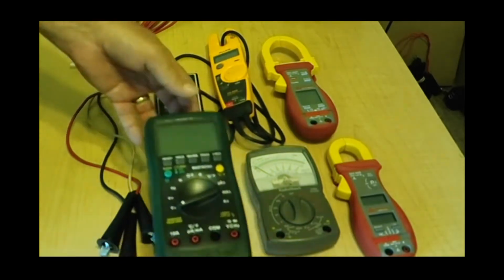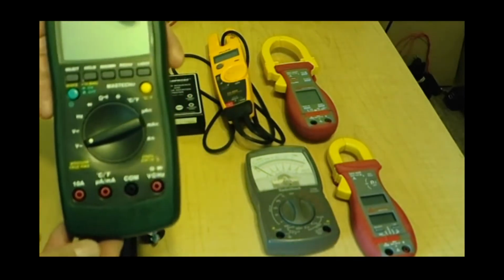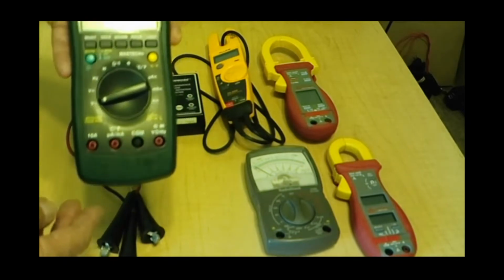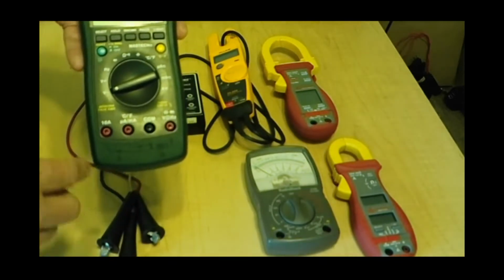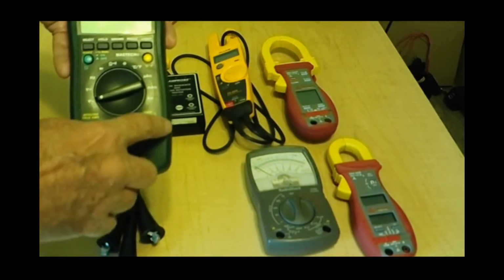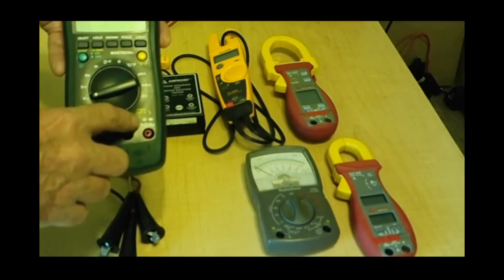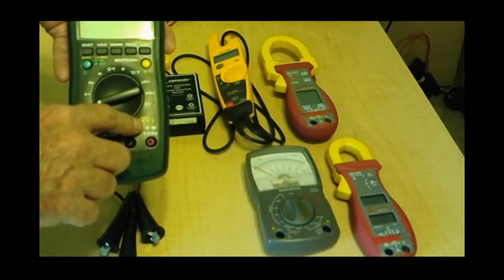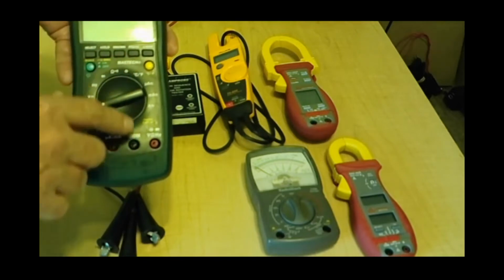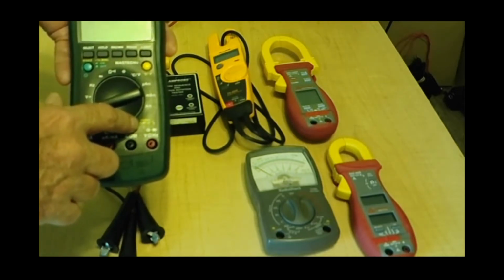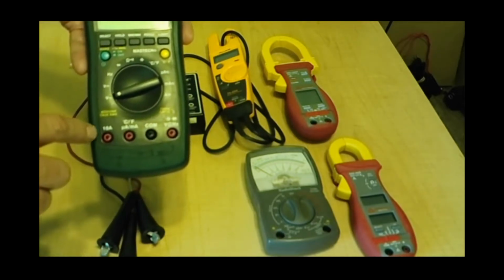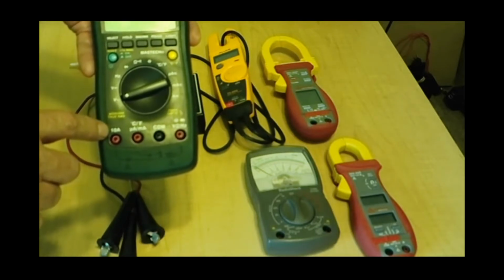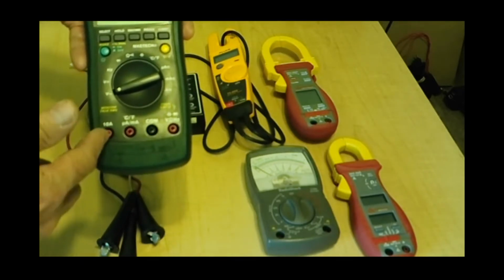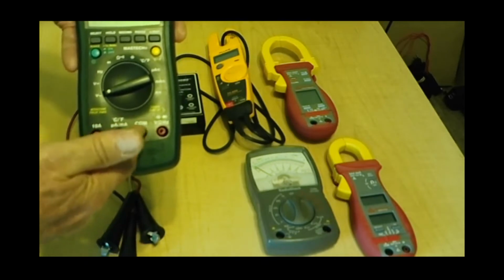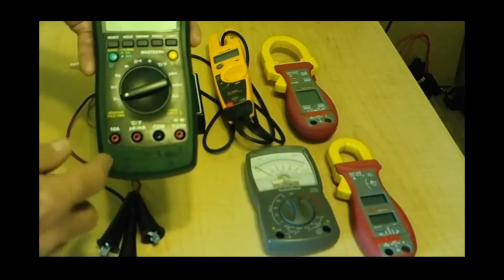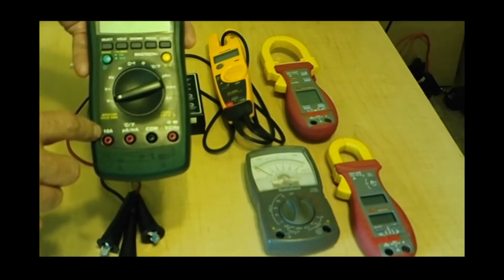Now, if I start with one meter right here, pretty common meter, I use this one because it can actually connect to a computer and go on screen. But this has got a voltage rating right here of no more than 1,000 volts. Anything above 1,000 volts will cause this meter to fail. If I want to read electrical current with this meter, this current will pass through the meter, in this terminal, out the common. So you have to interrupt the circuit, no more than 10 amps.